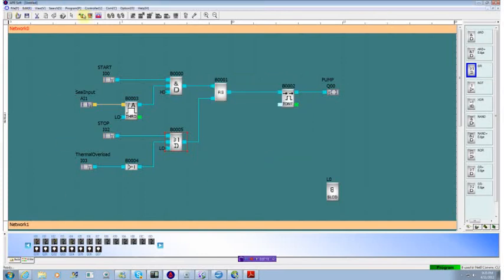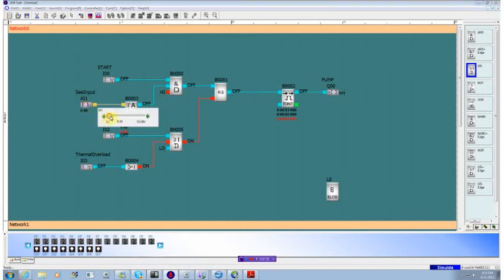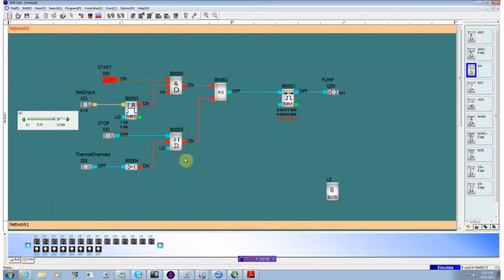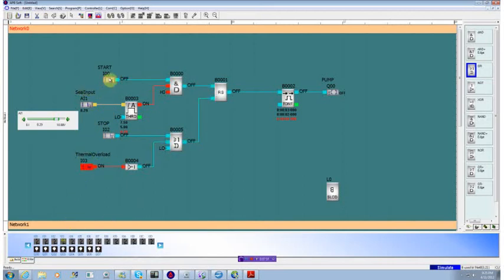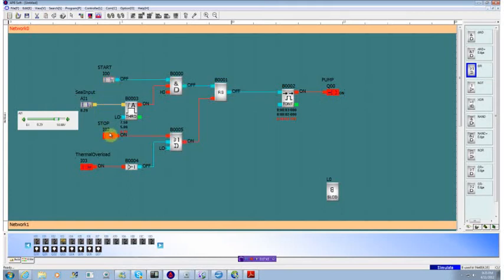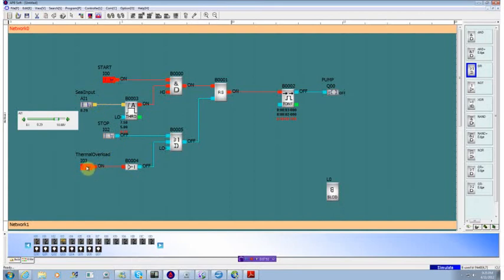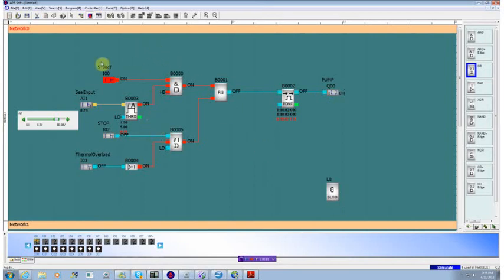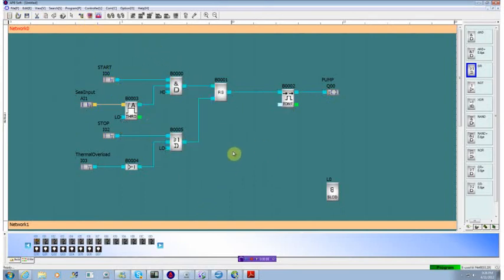Now when we start the simulator, we see that again we have to set our threshold above the preset level. We hit start, but our thermal overload is now disabling our motor from running because this should be a normally closed contact. So if we set this on, then hit start, our timer is running as we'd expect and the pump comes on. We can stop our motor, restart it, and let's say the thermal overload trips. Well, it trips and it sets the reset, but that leaves the timer stuck because it was still powering up and it hasn't got to even turning on the pump yet. So we need to change the logic around and the best way to do that is to simply reset this timer if this thermal overload should go off.